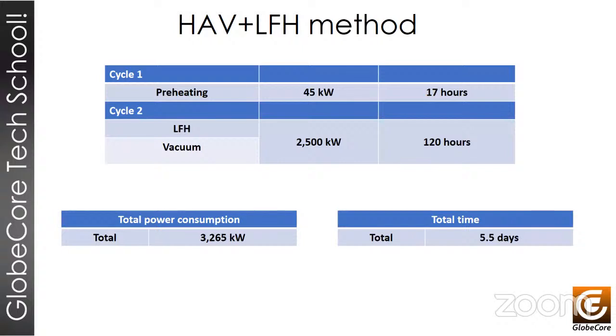This table contains the data of drying the winding in a vacuum oven using the HAV plus LFH method. We see the number of cycles totaling 2. We also see the power consumption within the cycle for vacuuming and heating. It's hard to avoid noticing that the number of cycles has considerably decreased. There is only one first preheating cycle. Next, the vacuuming and heating process occurs on a concurrent basis throughout the remaining time. In total, it took us 3,265 kilowatts of power to dry the winding and 5.5 days of the process duration.